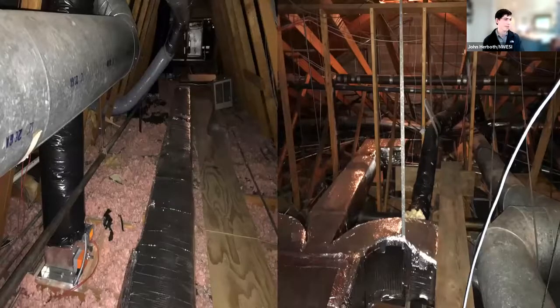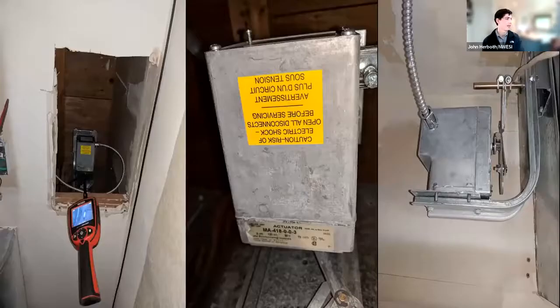Sometimes you have fun catwalks up in ceilings, some of them suspended, but there are plenty of dampers everywhere in different types of buildings. This is a Barber-Colman actuator, and we found this one scorching hot. You touch it and you'd scald yourself, and it had failed. There are several recalls on damper actuators. This one is one of those, and the internal gears had actually been fused together, so it was still drawing current and staying nice and hot in the failed position.